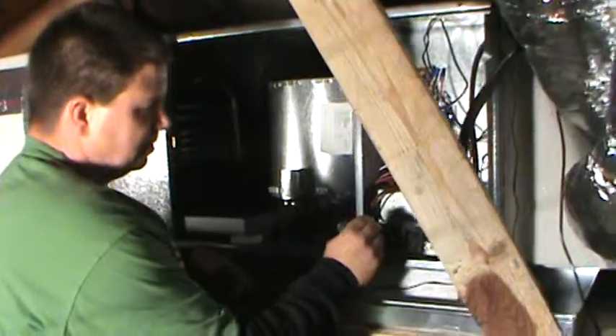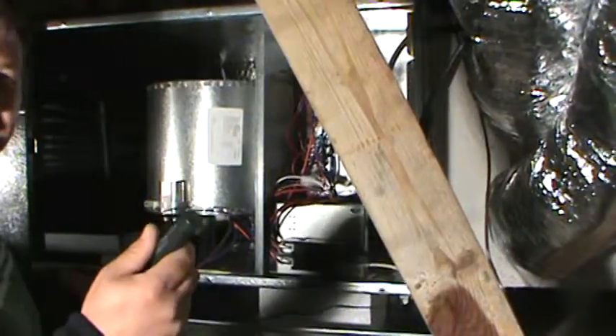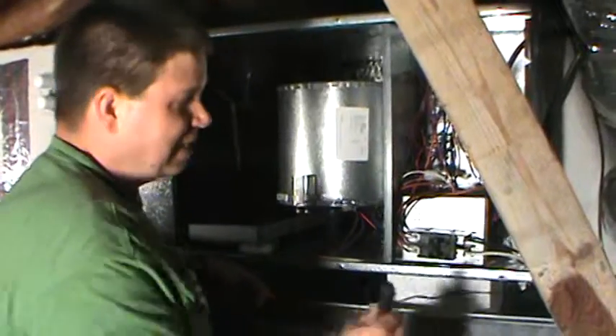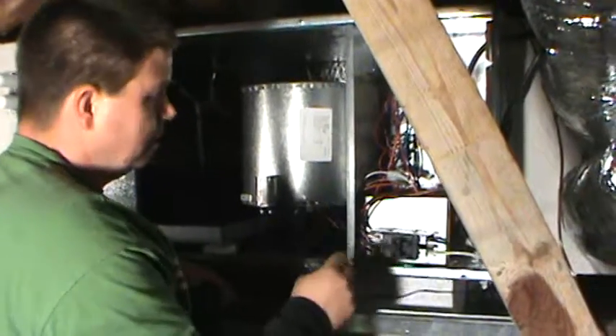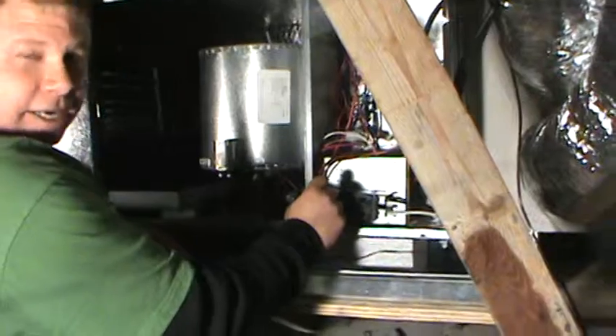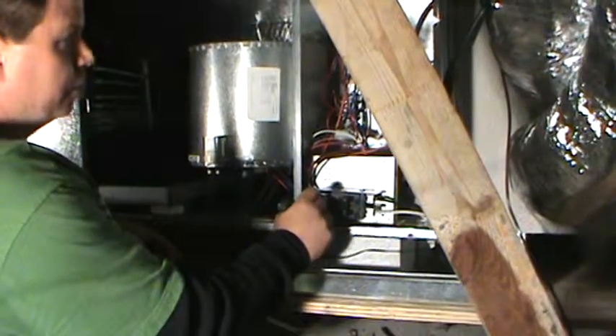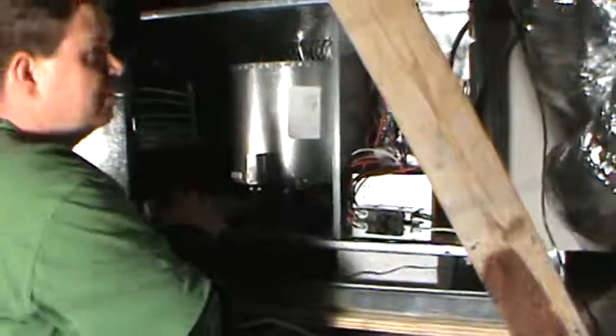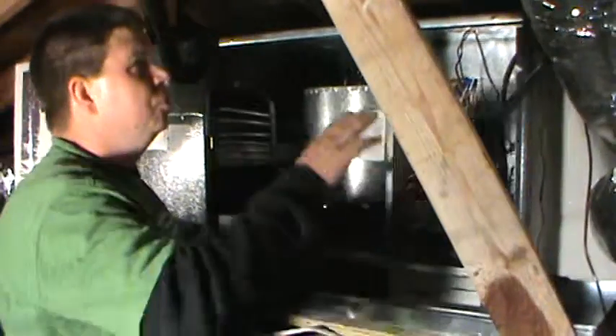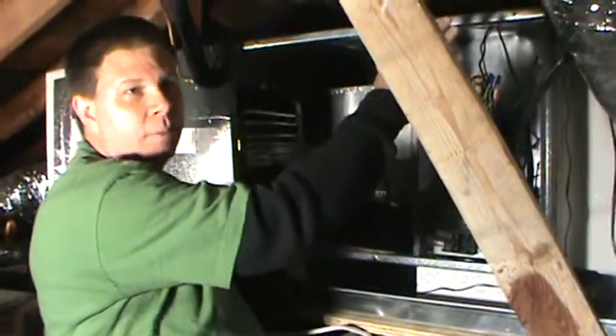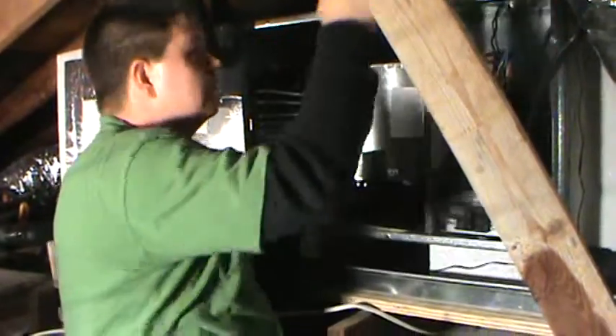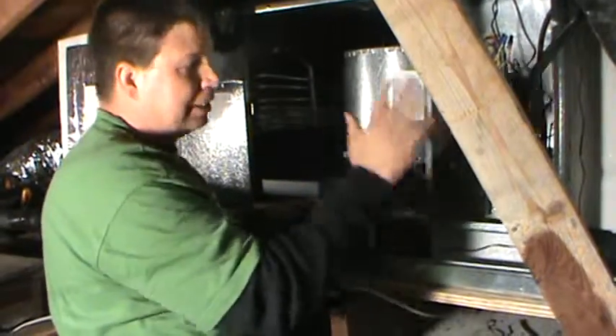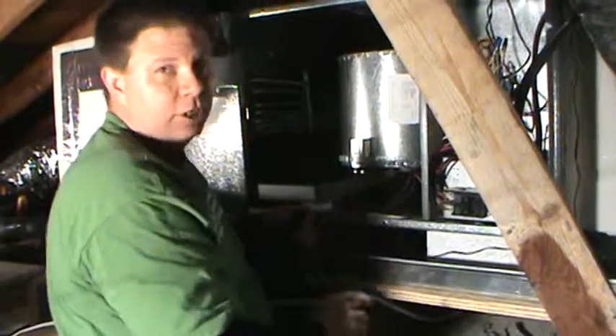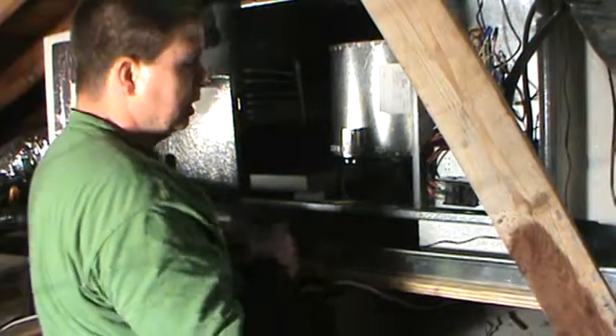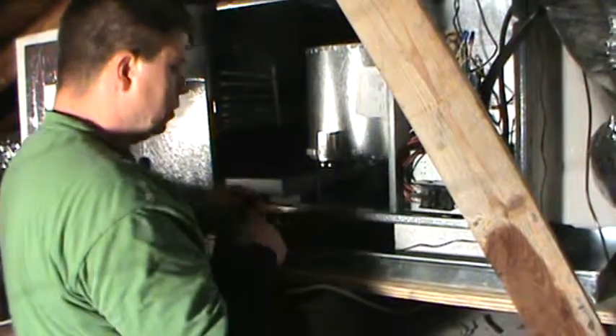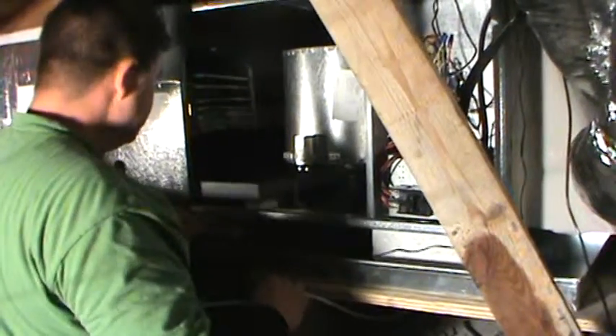So again, you just test. Make sure you test this in electrical somewhere where you know electric is at, and make sure it's working. But on our load side here, we are no power. At the disconnect, sometimes technicians will come in behind you and there's a problem with the disconnect and just wire past it. So you pull the pull-out out and you think, oh, there's no power here, but there could be, and very dangerous. So we've double checked, we have no power, and proceed.